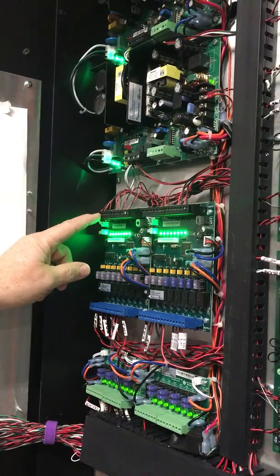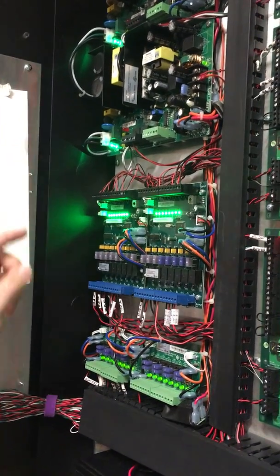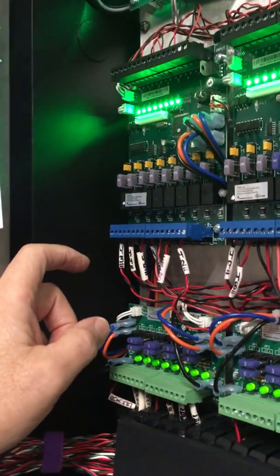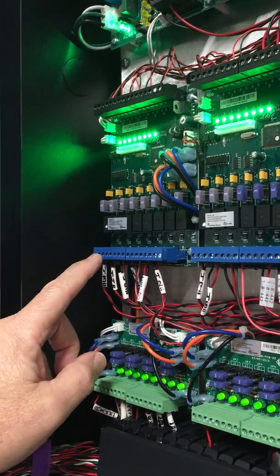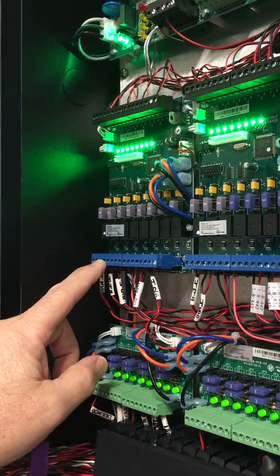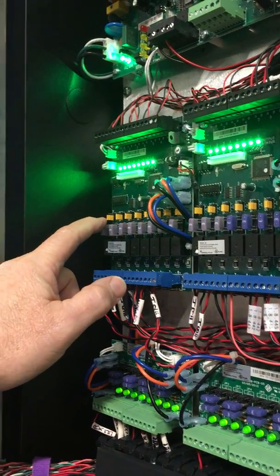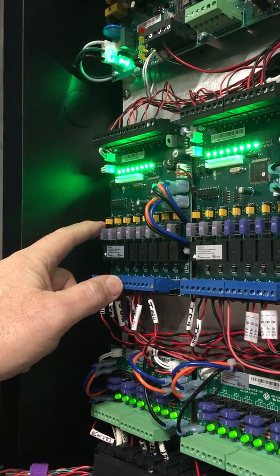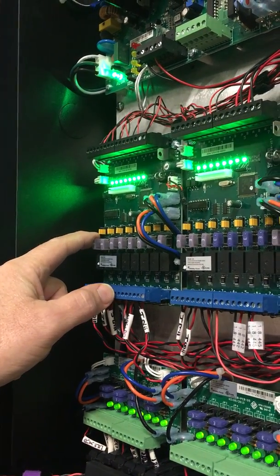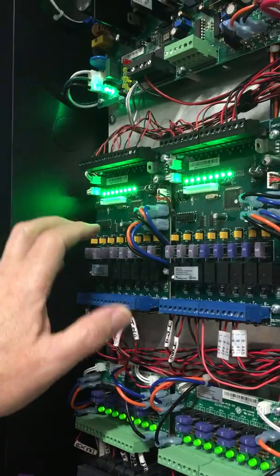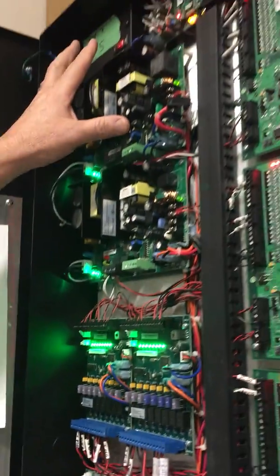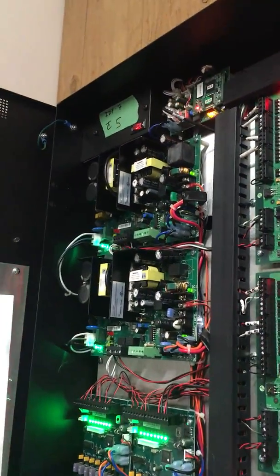The locks from the doors wire to the output, so output one and output two. You're gonna set the orange jumper to the lower setting, DC1. That makes the system draw power from the main power supply.